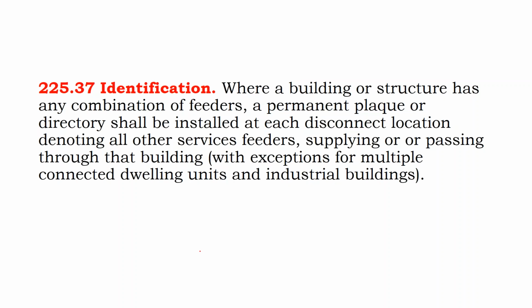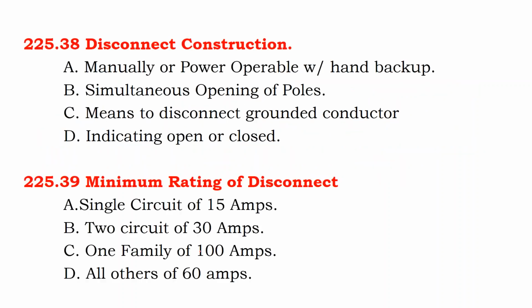And that's not just a solar requirement. What we see here on a more general basis is a requirement that when you have any combination of feeders feeding a building, there should be a plaque that tells the power company the location of those feeders. We're used to having our utility feeder circuit. Well, now we also have a solar circuit that's a feeder circuit. So supplying information at a readily accessible disconnect is a good thing, and we need to work with our utilities and fire departments to make on-site solar power something that they don't need to be so afraid of.